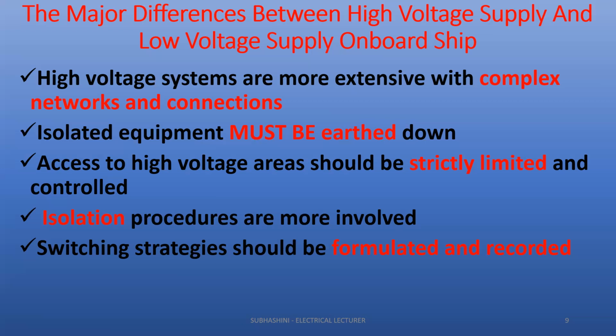Access to high voltage areas should be strictly limited and controlled. Isolation procedures are more involved. Switching strategies should be formulated and recorded. So what do we mean by switching strategies? In those times there were manually operated switching systems: how to open the circuit breaker, close the circuit breaker, earthings, and these things had to be done manually. Nowadays, it is done automatically. The electronic devices find out what the desired output value is, what output voltage is required. According to that, the switching strategies can be changed. The circuit breakers and these things can be switched automatically, and that has to be formulated and recorded. So on a routine basis, this has to be recorded.